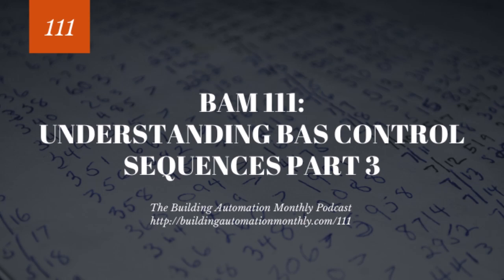You're multiplying that delta T times the GPM of that loop, and that gives you a BTU calculation that you can divide by 12,000 and get your tonnage. And then if you know the tonnage of the chillers, you're able to understand the load, and you're able to understand if you need to bring on more or fewer chillers, okay? That only works in certain situations.